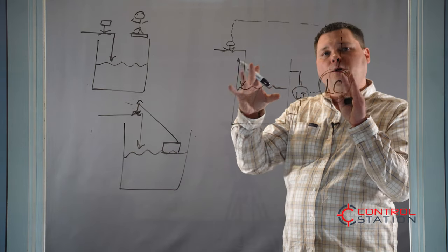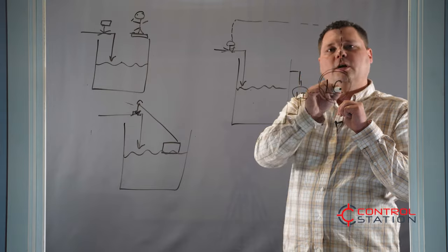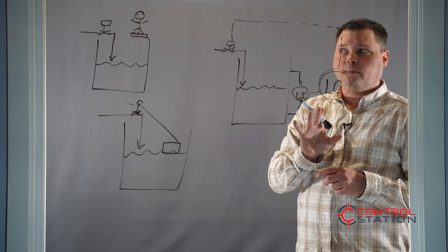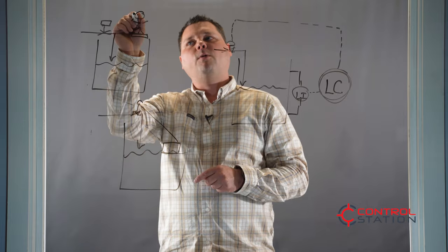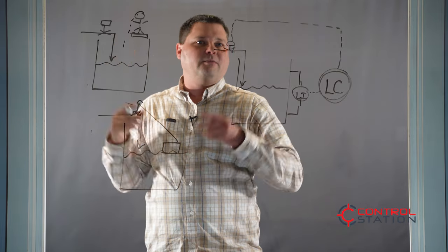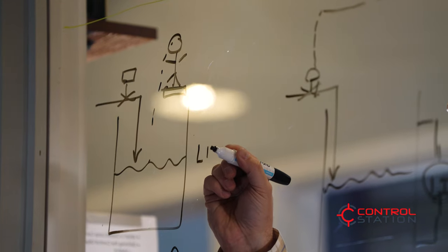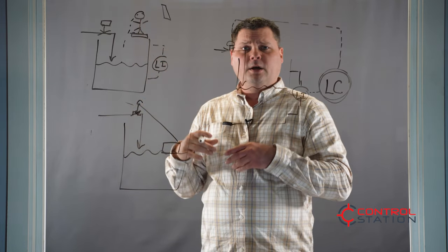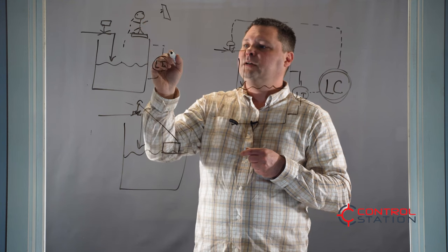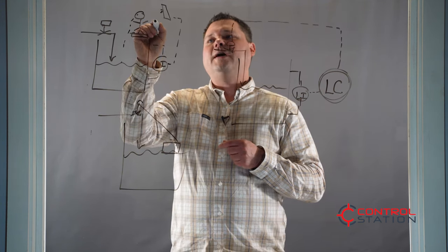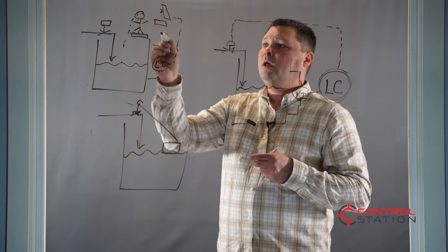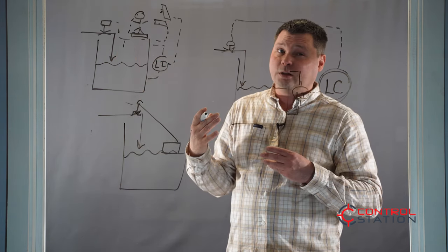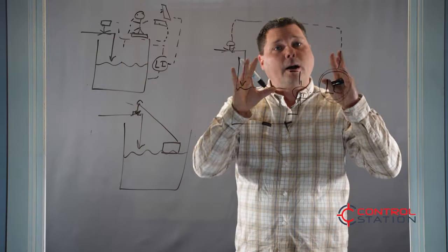This would be an automatic or closed loop system — the controller loop is closed. We're measuring the liquid level and feeding it back; that is a closed loop system. Going back to the manual example, the operator isn't physically looking at the level — there's probably some sort of level indication, and that information is fed to an operator station, an HMI, where they get a readout on the screen. There's usually a control console where they can open and close the valve directly from there without going out and physically operating valves. So this is manual control versus automatic control.